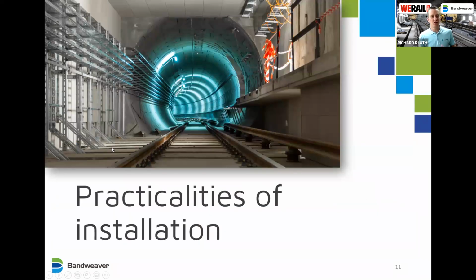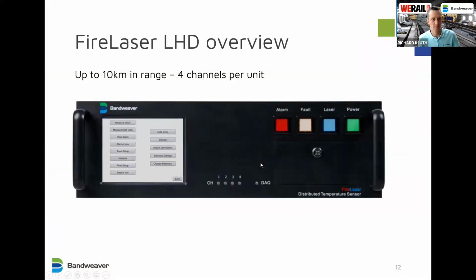So now we've sort of introduced the main components. Let's look in more detail at each of the components and the practicalities of how they work and how you would install it in a tunnel environment. So we'll start with the controller. The controller is the heart of the system. This is the Fire Laser by Bandweaver linear heat detection controller. This can go up to 10 kilometers in range, 4 channels per unit, so up to 40 kilometers, or 40,000 measurement points if you have it set at the 1 meter level.